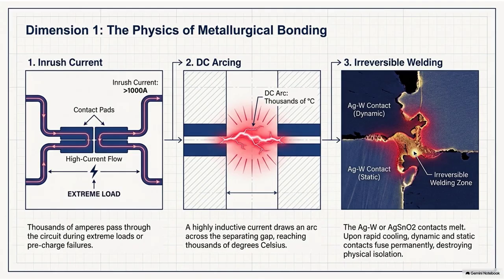However, hardware degrades. Of course it does. What happens if that pre-charge resistor has suffered thermal fatigue after 5 years of daily use? Or what if the BMS timer algorithms experience a fault, or a localized control circuit malfunction occurs? I see the vulnerability here. Because the BMS timer is just software. It might think, okay, 300 milliseconds have passed, the math says the capacitor must be full, but because the resistor is degraded, the capacitor is actually only halfway full. Exactly. The BMS, operating on faulty assumptions, issues the command to slam the main contactor shut prematurely. And boom. Boom. A massive residual voltage difference still exists across the gap. The resulting inrush current hits the metallic contacts like a sledgehammer, instantly exceeding the arc tolerance of the alloys, causing a transient high-temperature event, and once again, melting the contact solid.